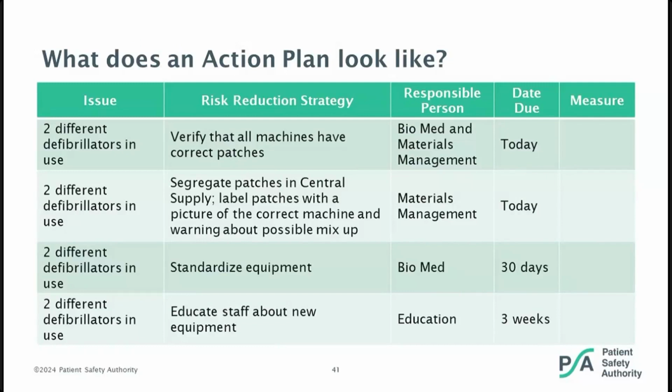Verify that all machines have correct patches, and we have a responsible person, biomed and materials management working together on this, and they're going to do that today to ensure that we have the correct patches for the correct machines. You might laugh. I'm not sure about your facility, but I've seen facilities that have had different types of monitors on different units, and each one uses different equipment. So something like this could happen.